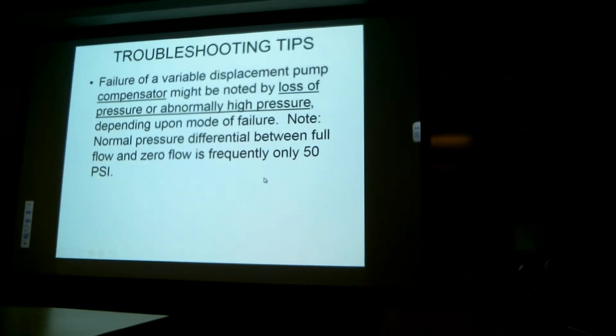You'd have to block the flow coming from the pump and then make an adjustment on the compensator. If you block the flow from the pump, that forces the pump to go to zero flow. So then, and only then, can you really adjust the compensator in order to provide for system pressure. So if you have to adjust a variable displacement pump that has a compensator in it, it's adjusted technically in the zero flow condition.